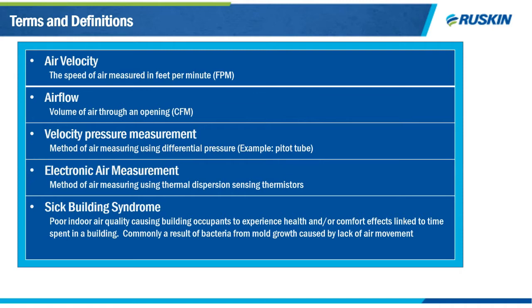We use a few common terms throughout this discussion. Air velocity is simply defined as the speed of air measured in feet per minute, and we use that to calculate airflow, which is the volume of air in cubic feet per minute through an opening. The two main types of airflow measuring systems are velocity pressure and electronic. Velocity pressure measures the difference in air pressure before and after a sensor to determine air velocity, and the most common example is a simple pitot tube.